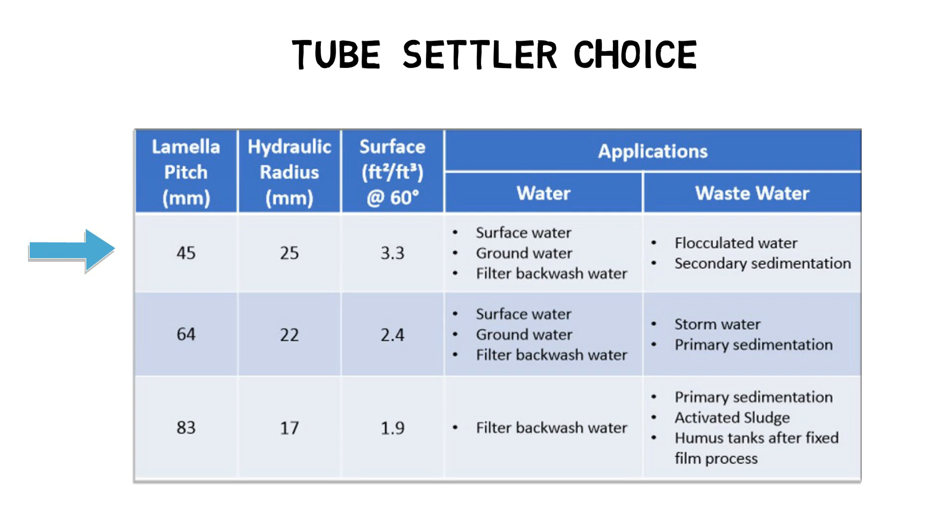This tube settler type has a channel distance of about 1.75 inches or 45 millimeters and a projected surface area of 3.3 to 3.5 square feet per cubic foot or 11 to 11.5 square meters per cubic meter. To determine the total required amount of tube settlers, the settling velocity of the particles has to be bigger than the water flow divided by the total projected surface area of the tube settlers.